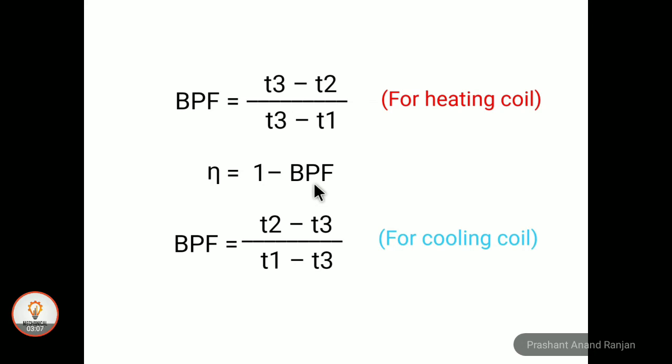Here the efficiency of the heating coil can be calculated as 1 minus BPF. As BPF represents the loss, 1 minus loss represents the efficiency. Similarly, for the cooling coil we can write it as T2 minus T3 divided by T1 minus T3.